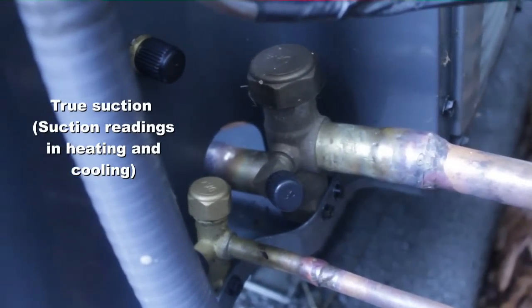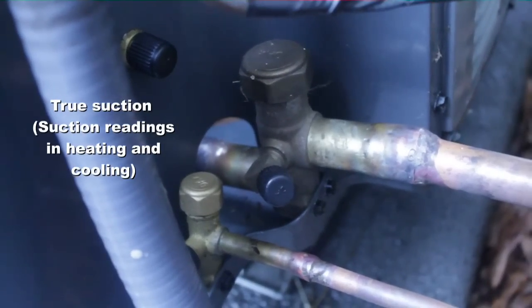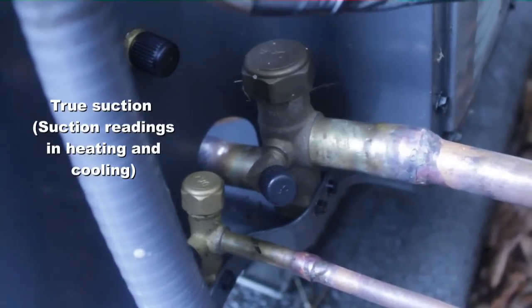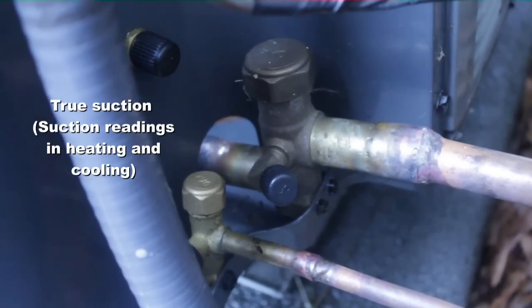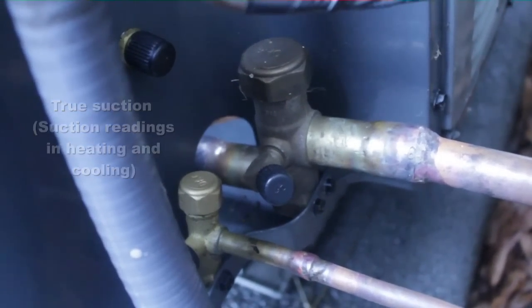I generally charge in cooling at the suction service valve because there's less of a chance that liquid refrigerant will be a factor getting into the compressor. It just gives it a little bit longer run before it gets there. Of course, you may use some device that causes it to turn to vapor before it gets into the line.